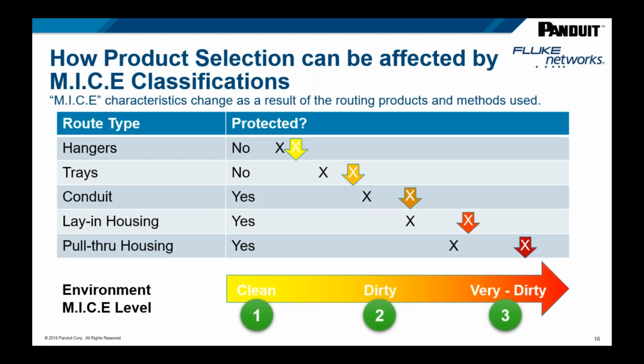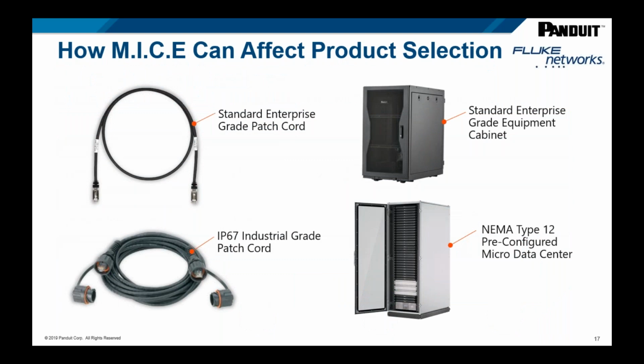To give you a couple of examples of how M.I.C.E. can be implemented, one way is with hardening of equipment and how we route the cabling. An easy way to understand that is in terms of the pathways used. In a M.I.C.E. level 1 environment, more of an office type environment, we may be using things like hangers and trays. As the environment gets harsher, looking just at mechanical and ingress, we may go to conduit. And if we need a more sealed environment, we may go to lay-in housing or a sealed wireway. So this shows how you can use different levels of hardening to address the M.I.C.E. elements, while still using that same cabling.